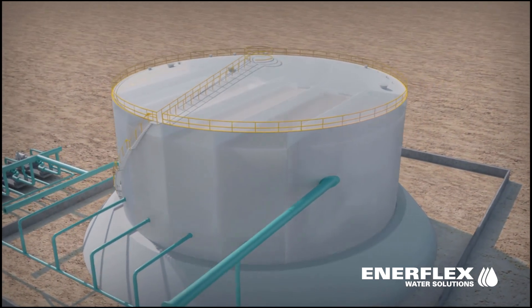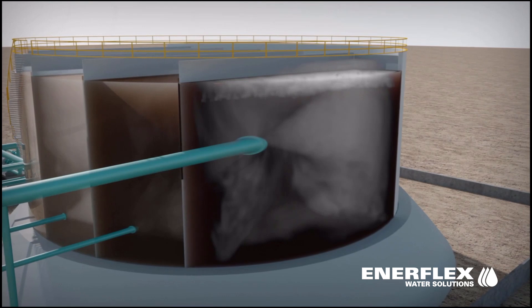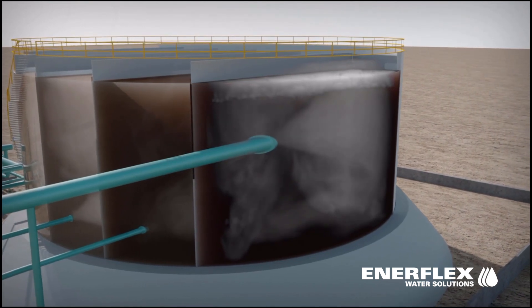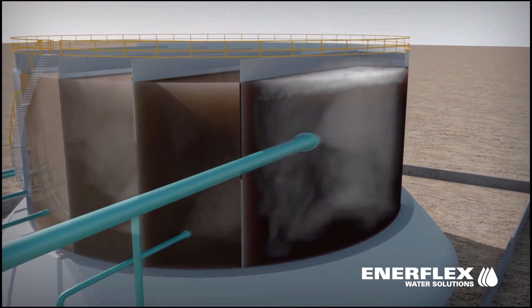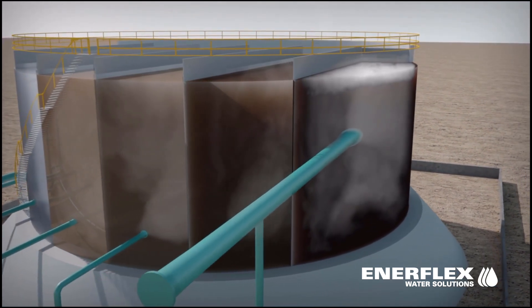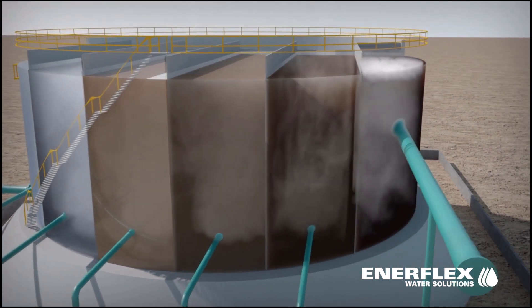The EGFT is divided vertically into six water process chambers and one skimmed oil chamber. Produced water enters the chambers sequentially and microbubbles are introduced. Oil is lifted upon the bubble layer and is skimmed off by overflowing an oil weir.